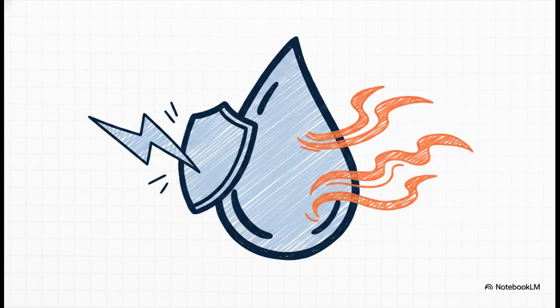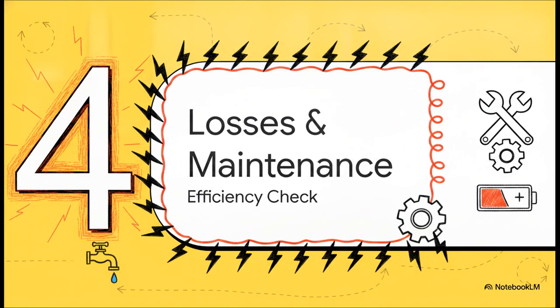Of course, we really can't talk about cooling without talking about the transformer oil itself. This stuff isn't just a basic coolant. Whether you're using a standard mineral, hydrocarbon, or some expensive, non-inflammable synthetic liquid, this oil is actually acting as a primary electrical insulant and the main thermal transfer agent inside the tank. All right, moving on to Section 4, losses and maintenance.